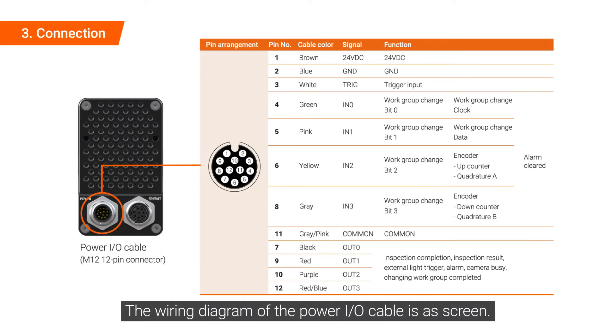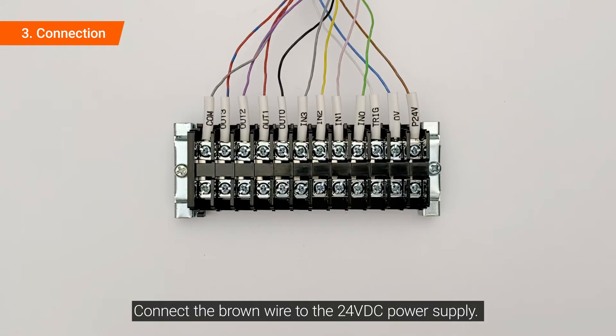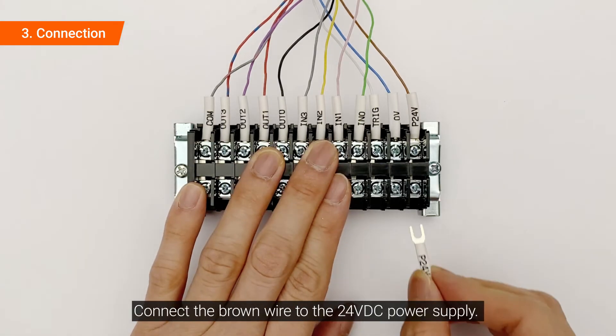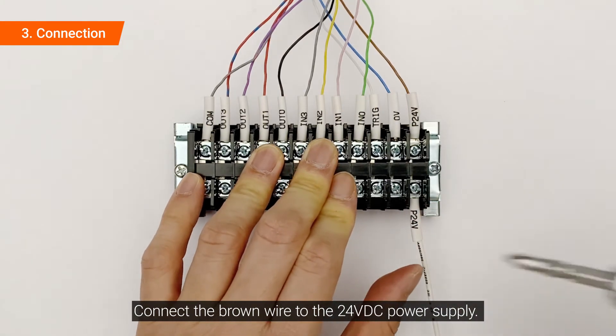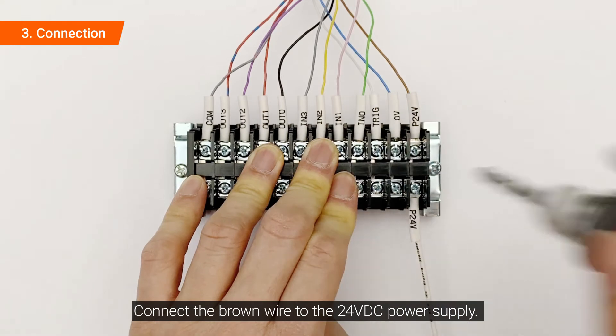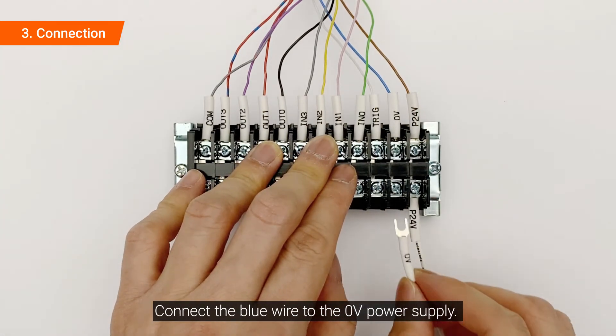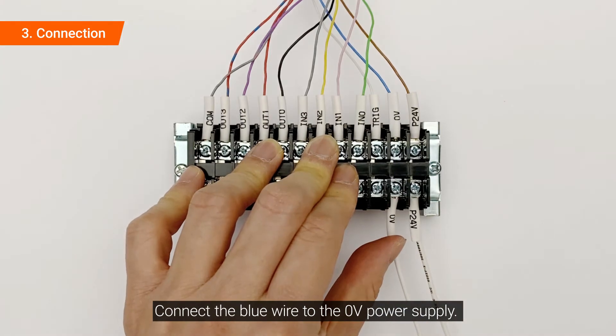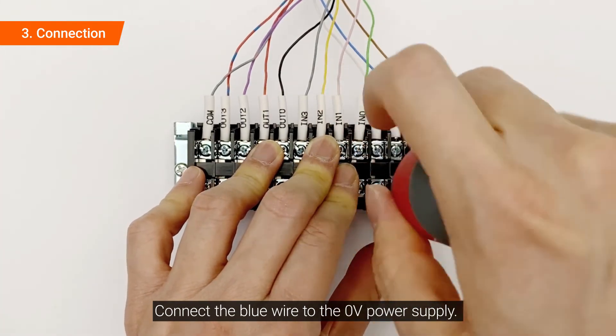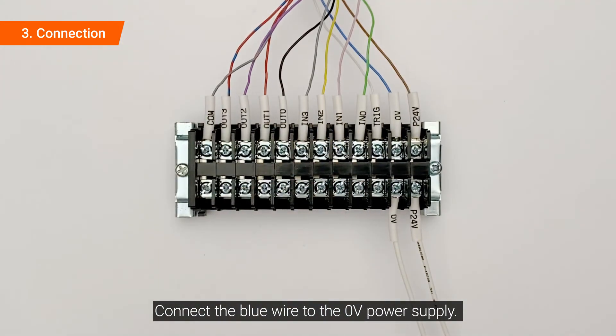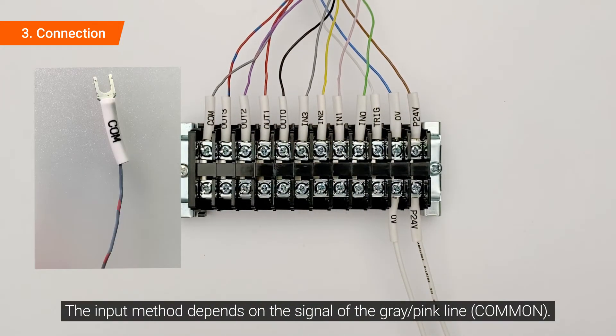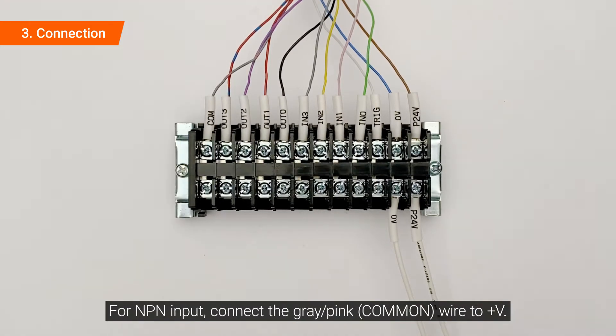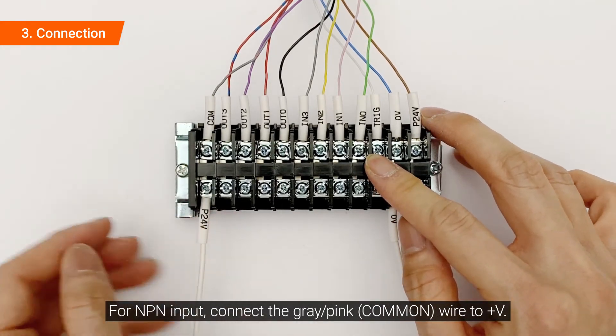The wiring diagram of the power I/O cable is as shown on screen. Connect the brown wire to the 24V DC power supply. Connect the blue wire to the 0V power supply. The input method depends on the signal of the gray-pink line. For NPN input, connect the gray-pink wire to plus V.